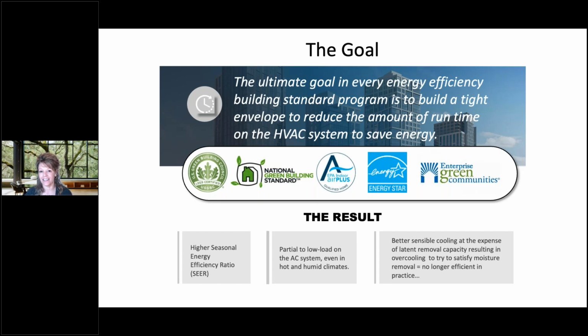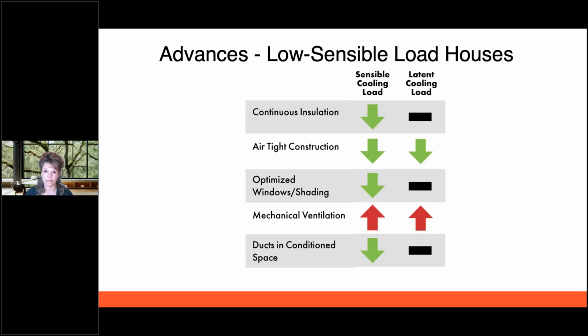But it's at the cost of removing the latent load. The shorter the run times, the less water that we are going to remove. So advances in low load homes are really advances in low sensible load houses. We have continuous insulation, driving down that sensible cooling load, and airtight construction. That's helping with driving down the sensible cooling load and the latent cooling load by not allowing air to infiltrate from the outside when that hot goes to cold.